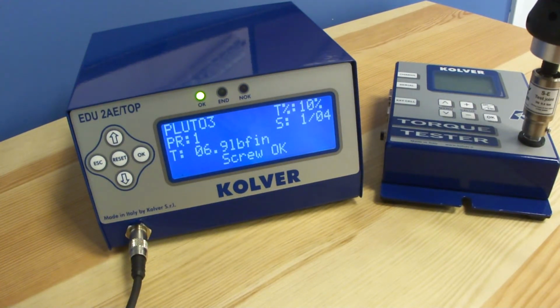What is important to remember about the calibration procedure with the EDU2AE top is it does need to be done for each of the individual 8 programs to ensure accurate readings. It's common to think that because the calibration procedure is done for program 1, that it will carry over to the remaining programs, but this is not the case.